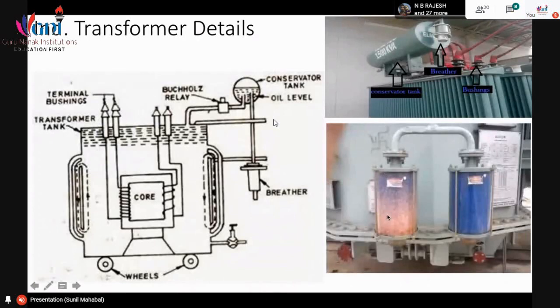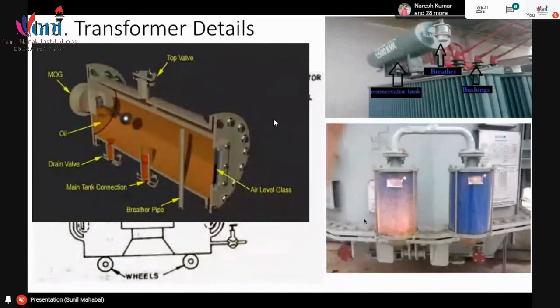Now this is how the conservator looks from inside. The oil is inside the conservator, with the drain valve, main tank valve, and breather pipe. This pipe is connected here. It is actually taken from the top of the tank. Then this is the MOG, magnetic oil gauge. Why is this magnetic type of oil gauge used? So that the flange of this conservator need not be punctured. Otherwise, you will have to puncture it, and then there will be a possibility of oil leakage. To avoid that, this is a magnetic type oil gauge.